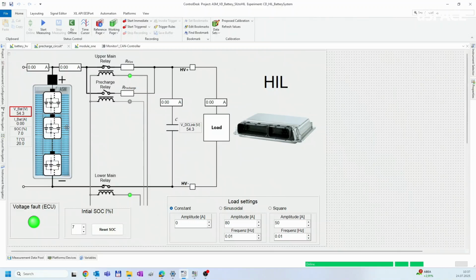Now you can see a window showing our instrumentation software ControlDesk. The layout shows the pre-charge circuit and battery voltage and current. In this demo, we want to provoke the ECU to raise an error flag when the total battery voltage falls under the minimum allowed and configured voltage of 53 volts. To approach this border, we will simply draw a continuous current out of the battery. Once the border is reached, the BMS is supposed to stop the current flow by opening the main contactors.